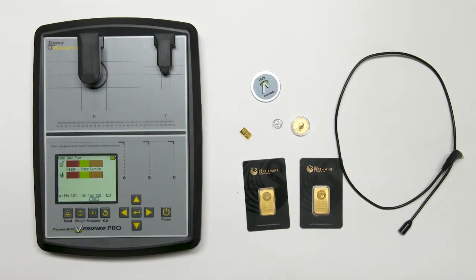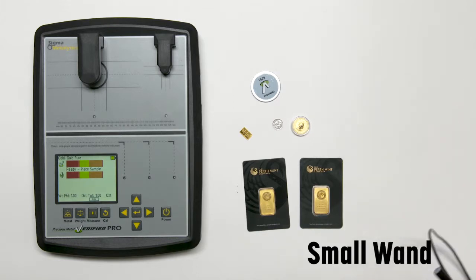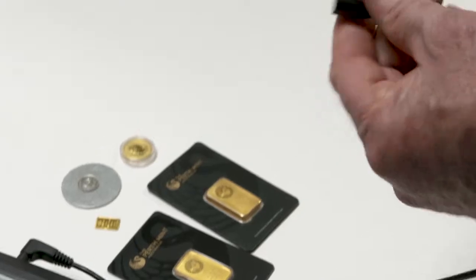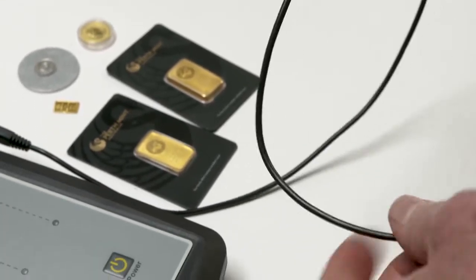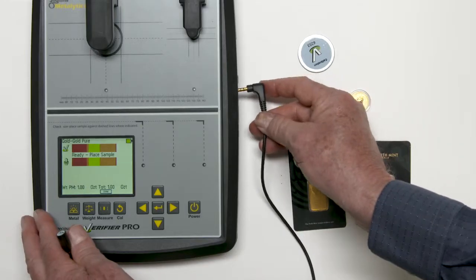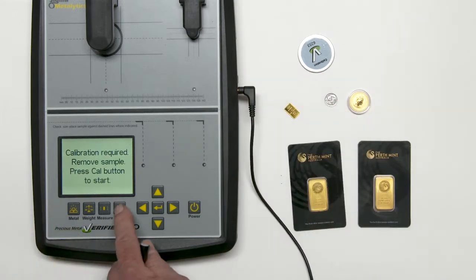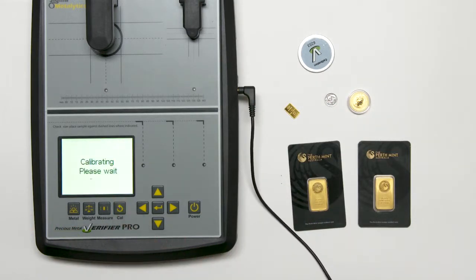Another wand that can be used with the PMV Pro is the small wand, which is also found on the standard PMV. This is used for samples similar to the micro wand. It can't go quite as small as a micro wand because this sensor is 7 millimeters in diameter. However, it has some advantages, so I want to demonstrate that.